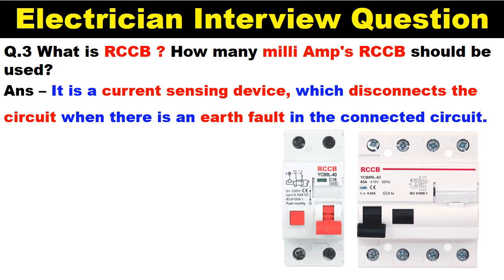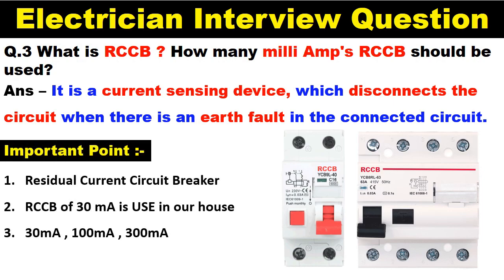Your answer should be: RCCB is a kind of current sensing device which disconnects the circuit due to an earth fault in a connected circuit. As for how many milliamperes RCCB to use — 30 milliampere RCCB is used in our home. In industries, 100 milliampere RCCB is also used, because 30 milliampere RCCB trips too often, and to reduce this tripping, 100 milliampere RCCB is used.